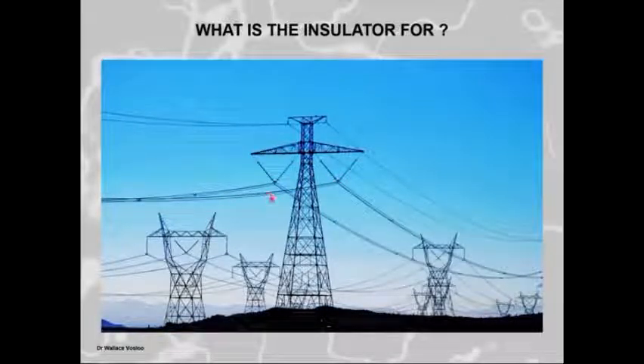There are vibrations which take place in this conductor, which at the end of the day are transferred to all these fittings and all the hardware down on the live side. And you will see that from the electrical side, we have to reduce the stresses by putting on corona rings to reduce the electrical stresses. And this insulator is not in a clean environment. We've got the wind, we've got the rain, we've got the lightning. We can have birds sitting up here excreting into the gap, causing an air flashover process.